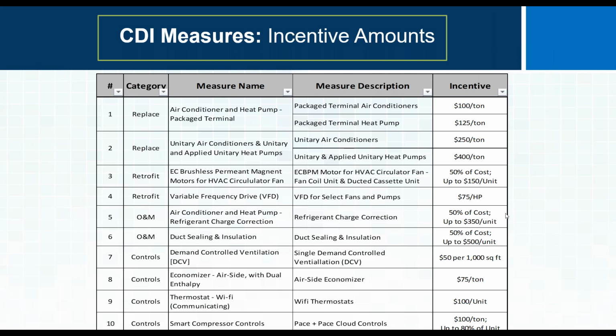Measures 3 and 4, guys, retrofits. This all has to do with making our motors controllable. For smaller motors, we can replace them with EC motors, electronically commutated motors, typically for motors of 1 horsepower or less. Larger motors, where we want to retrofit and add controllability, can make use of VFDs, variable frequency drives.